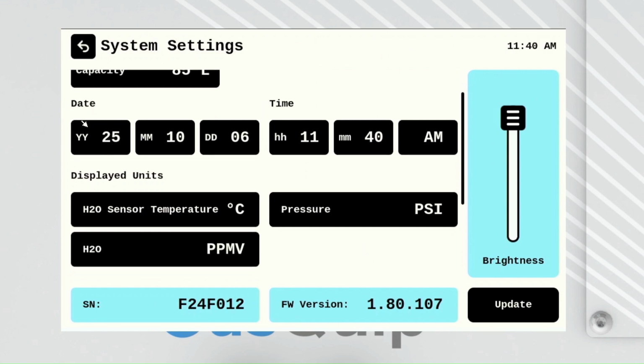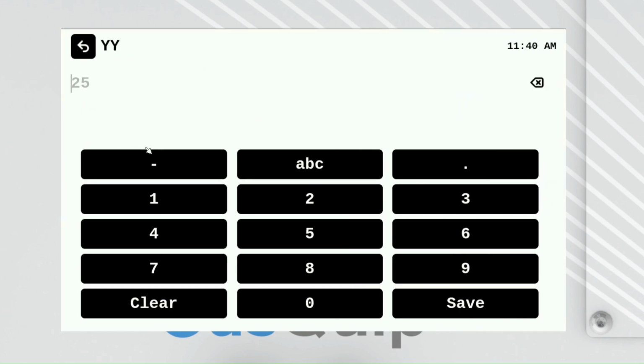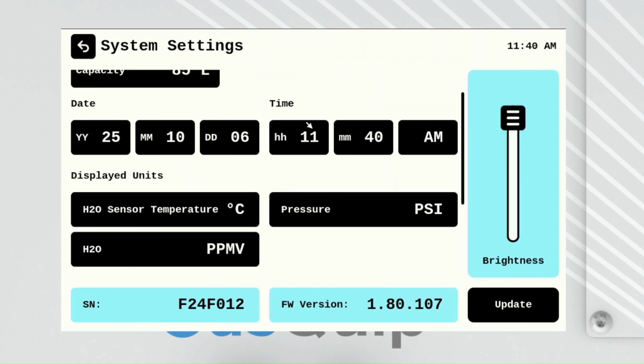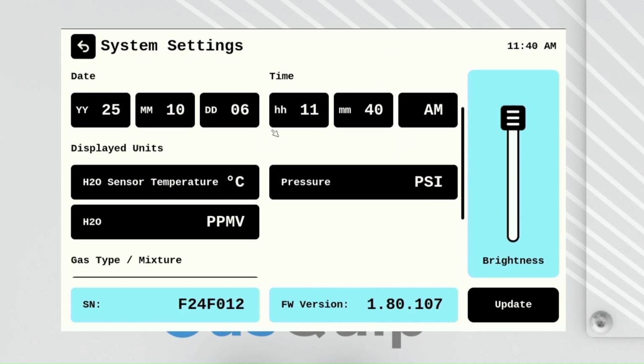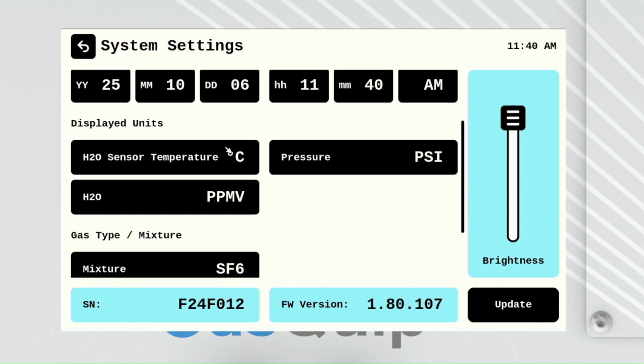you can change that. Date and time, if you click into the individual boxes, you can change the date and time, and then also toggle our AM, PM to whatever you need. The displayed units for H2O sensor temperature can be toggled just by clicking to the box. It's defaulted to degrees C. Our input pressure on the home screen, you can toggle this to whatever you need. And then same thing with the H2O module readout, it can be changed here. And then also while a test is running and on the log test screen as well.